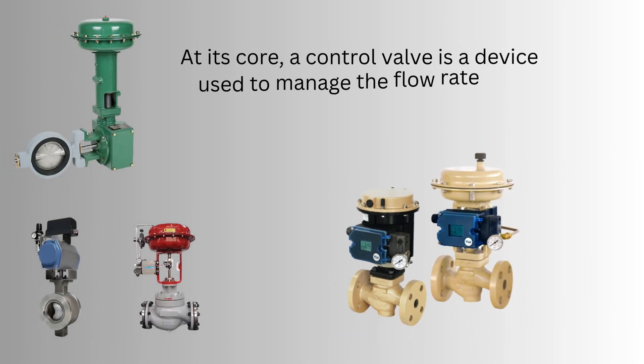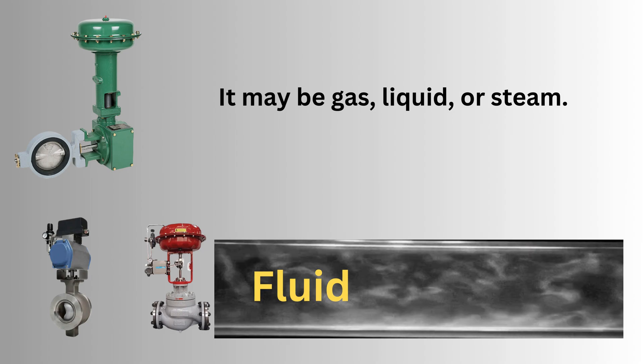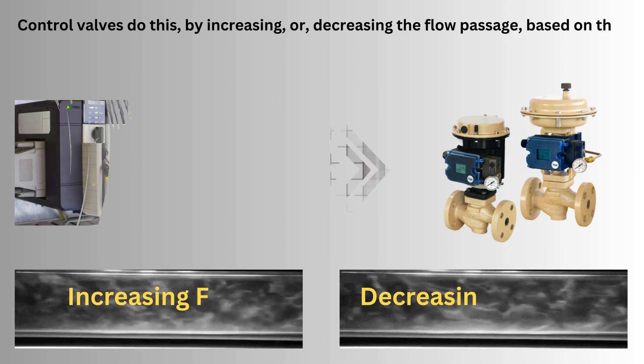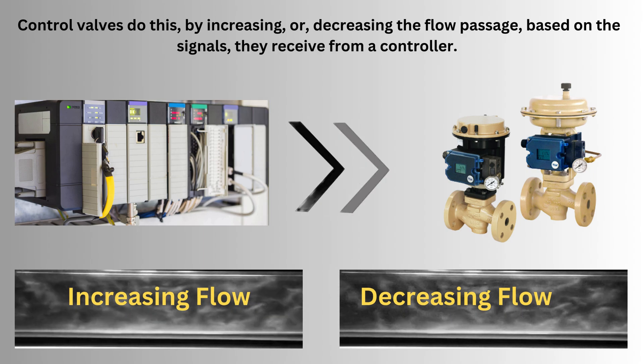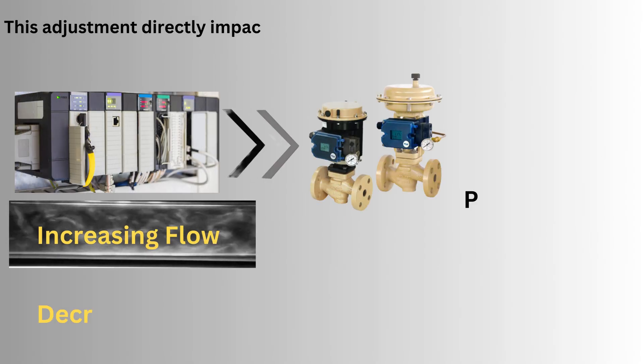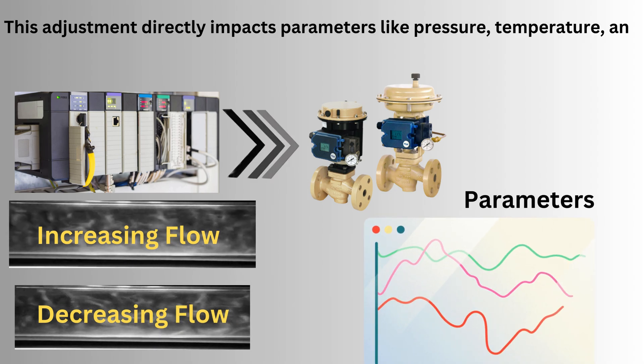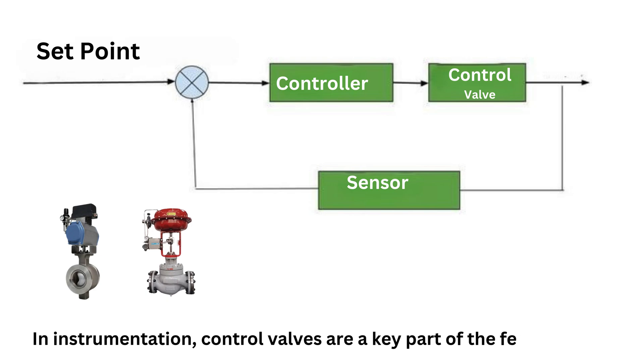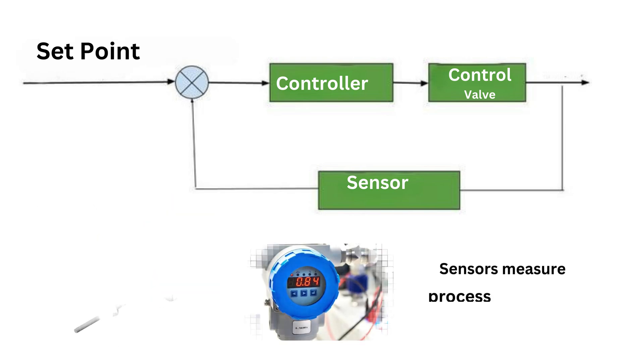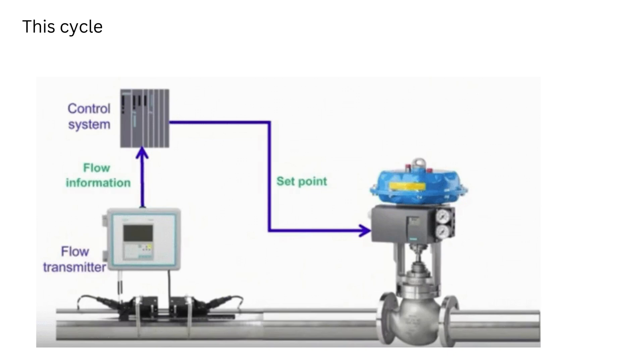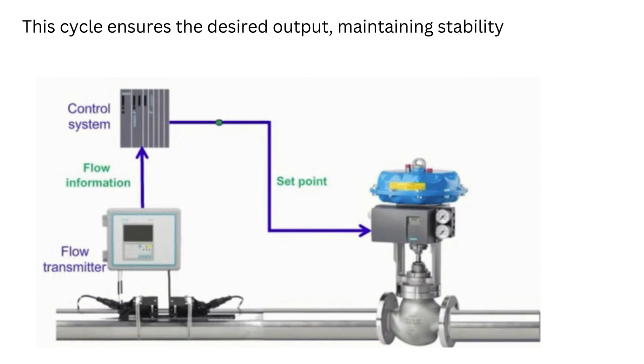At its core, a control valve is a device used to manage the flow rate of fluids — it may be gas, liquid, or steam. Control valves do this by increasing or decreasing the flow passage based on the signals they receive from a controller. This adjustment directly impacts parameters like pressure, temperature, and liquid level. In instrumentation, control valves are a key part of the feedback loop: sensors measure process conditions, the controller sends a signal, and the valve adjusts accordingly. This cycle ensures the desired output, maintaining stability in the system.